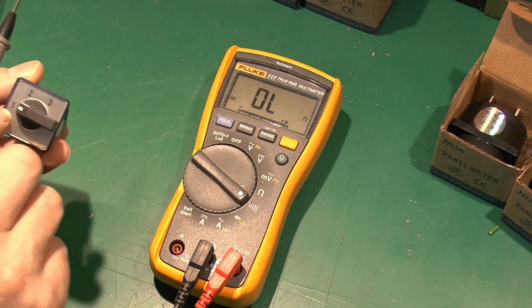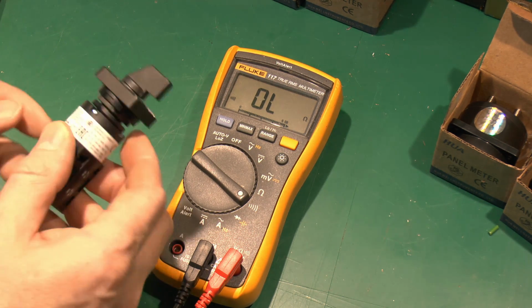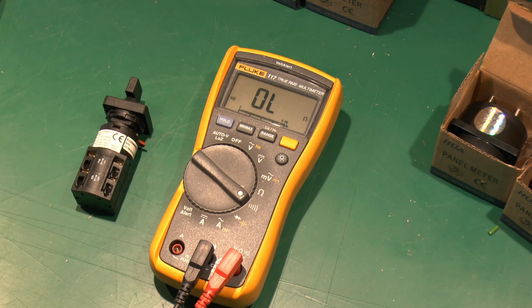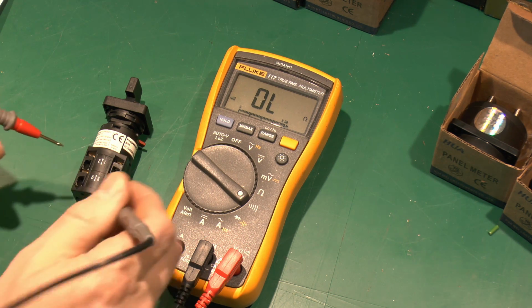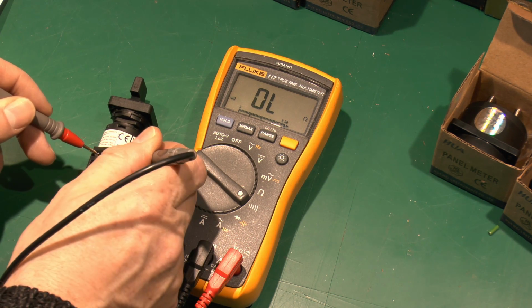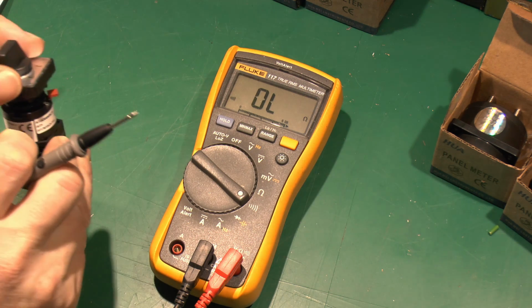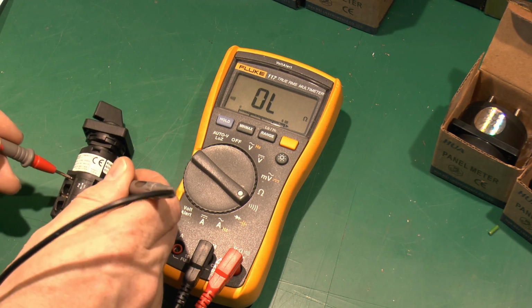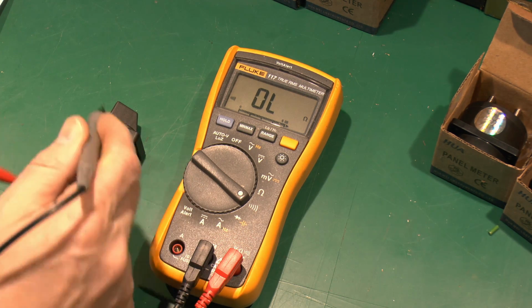Now in terms of positioning, we'll select position 1 on the switch here, and according to the information, the output when in position 1 is in fact number 1, so we check between 2 and 1, we should have continuity. We do. If we now move the switch to another position, continuity has gone away, so that's on position 2 now.